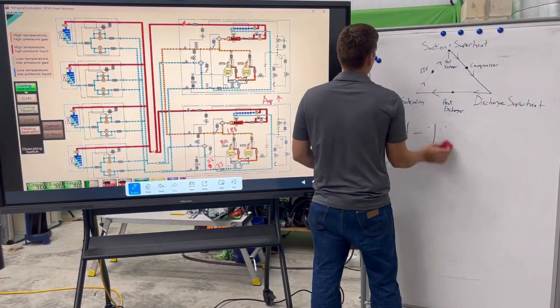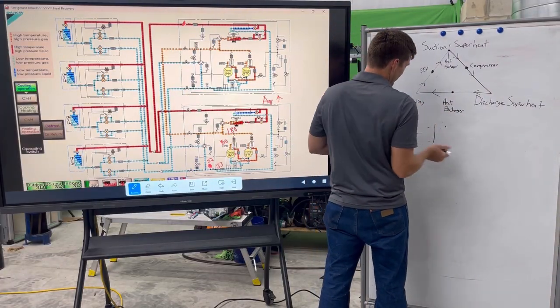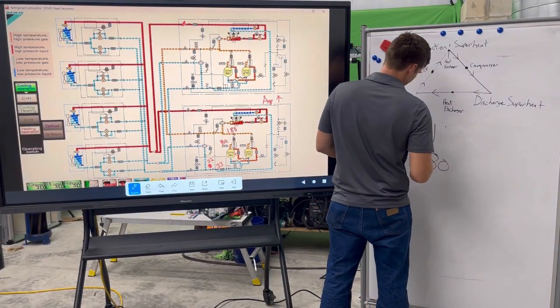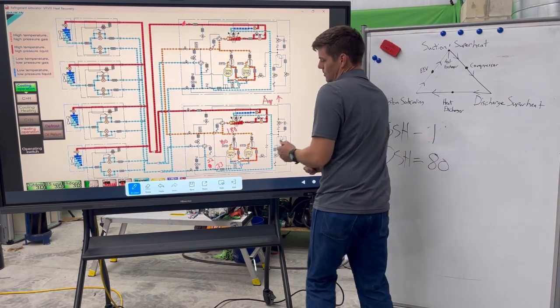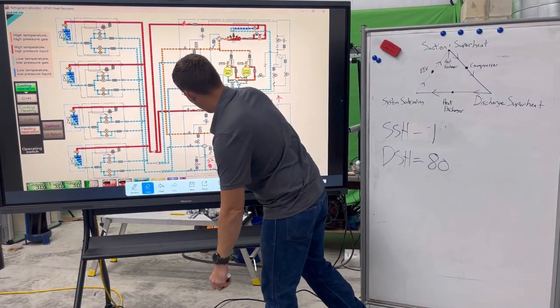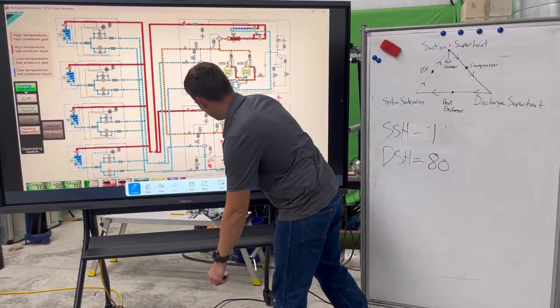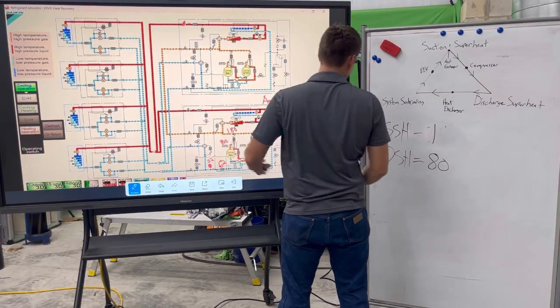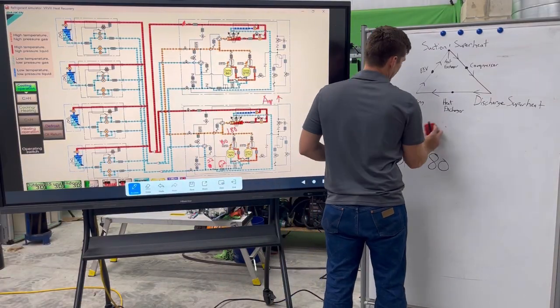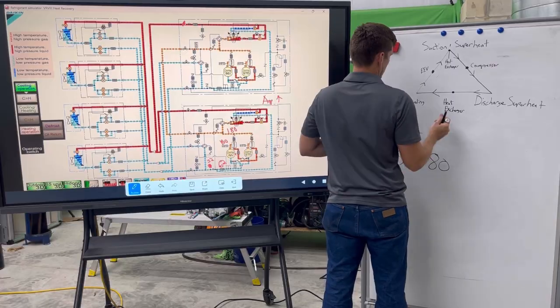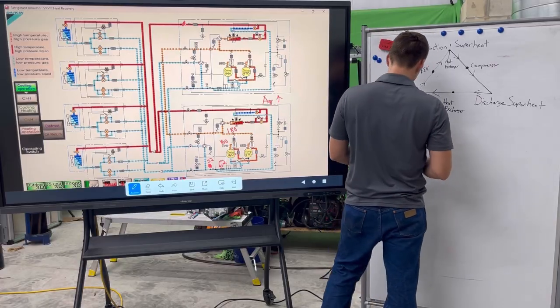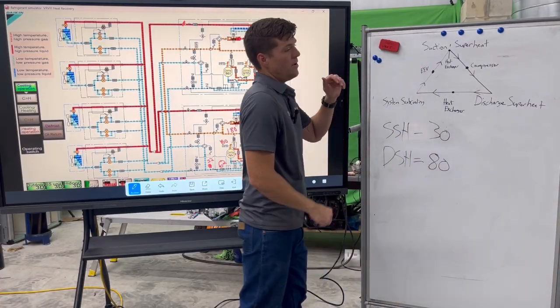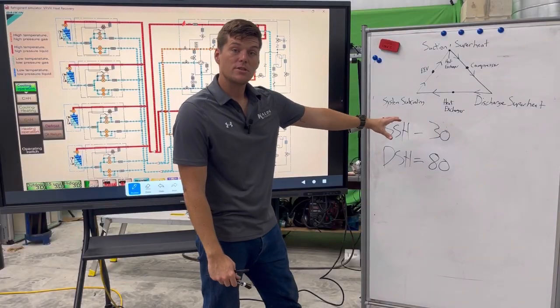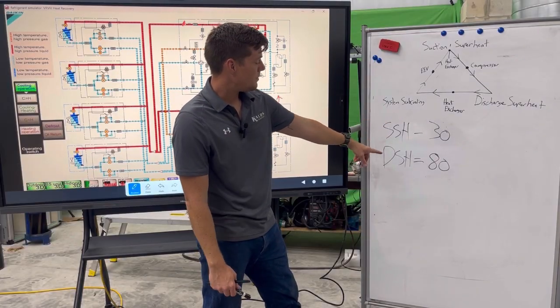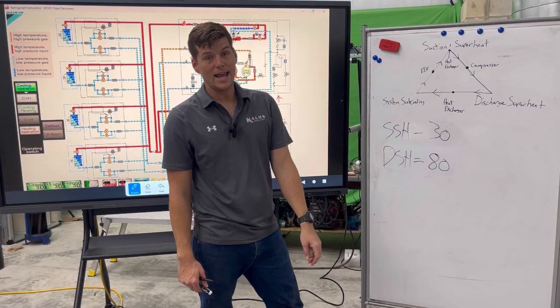Well, that puts me at a discharge superheat of 80. And let's change our suction superheat back to where we were before, and that was 62. With being at 62, we're going back to the beautiful number of 30 degree suction superheat, which is more realistic on what you're going to see in your average system. So we know we have elevated levels of suction superheat, 30 degrees. We have an elevated level of discharge superheat, 80 degrees.